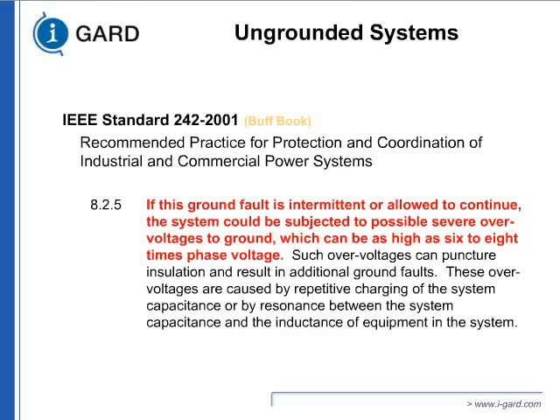One good thing in an electrical system is, and I'm not being sarcastic, all faults are self-clearing. That means anytime a component fails, the system will go into shutdown mode. This happens with intermittent ground fault because of the resonance. Then you have a red book, which is designed for power system design. Okay?